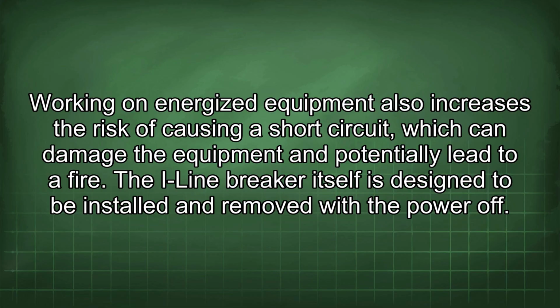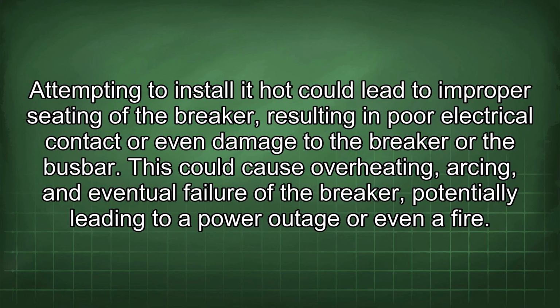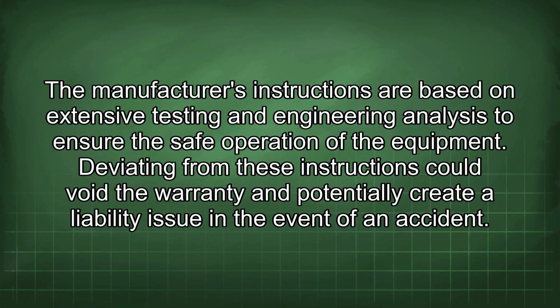The I-Line breaker itself is designed to be installed and removed with the power off. Attempting to install it hot could lead to improper seating of the breaker, resulting in poor electrical contact or even damage to the breaker or the busbar. This could cause overheating, arcing, and eventual failure of the breaker, potentially leading to a power outage or even a fire. The manufacturer's instructions are based on extensive testing and engineering analysis to ensure the safe operation of the equipment. Deviating from these instructions could void the warranty and potentially create a liability issue in the event of an accident.